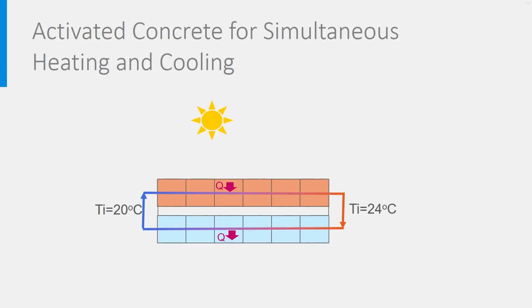A nice feature of activated concrete is that it can be used as a passive heating and cooling system in buildings that need simultaneously heating and cooling. This happens a lot, for instance, if a part of a building is oriented to the sun and needs cooling, while another part of the building needs heating, like on the picture. The rooms at one side of the corridor become too warm and need cooling, while the rooms at the other side are still too cold. It can happen in school buildings.